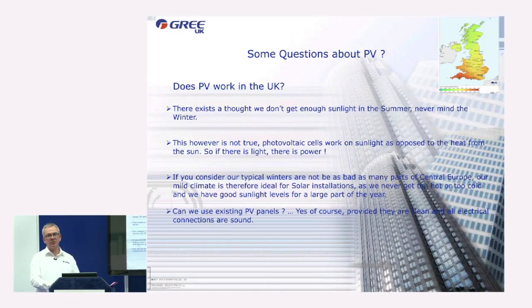Can we use existing PV panels? Simple answer is yes. Obviously, with PV panels, there's very little maintenance. As long as they're kept reasonably clean and not covered in dust and dirt, and the connections are sound, there is no reason why you couldn't use an existing array of panels. Simple connection, straight to the DC connection on the outdoor unit.